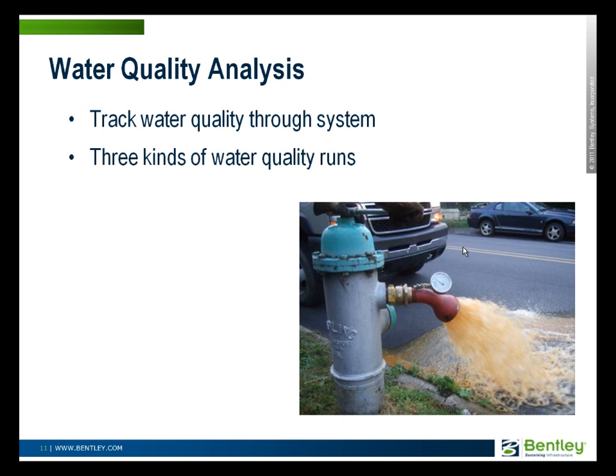Water quality analyses are another kind of run of a water distribution system model. In this case you're tracking water quality through the distribution system — not just estimating pressures and flows, but calculating the water quality aspects of the distribution system. There are three different kinds of water quality runs that can be done in WaterGems. The first and most simple is age — just how old is the water? A lot of times this is about all you need. You're basically using this to figure out where you're likely to have old water in terms of chlorine residual or disinfectant byproduct formation. Age is a good indicator: the places with the oldest water are where you're going to have the most serious water quality issues.